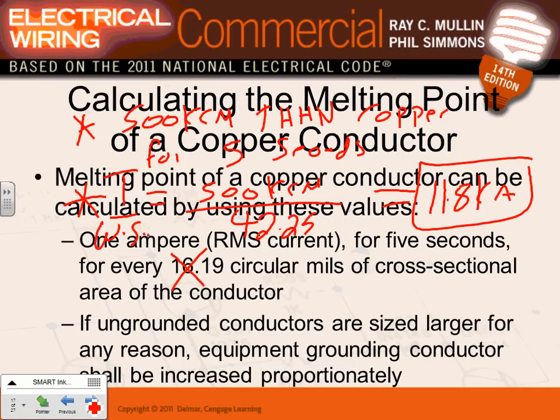Any comments, any questions? This number here that you see, 16.19, that's when the copper starts melting. That's why we don't use it. The good news is all these numbers, you guys don't have to memorize them. When you have the software, all you have to do is grab the conductor, 4-aught, 500, and as you grab it, visually, graphically, the system will draw a line like this for you.